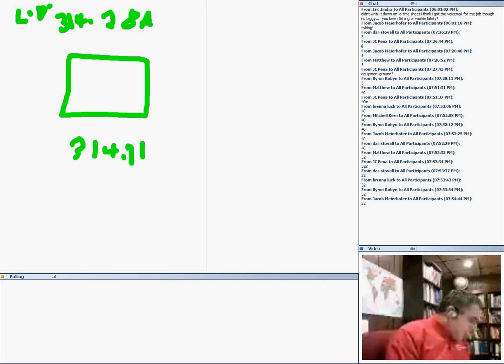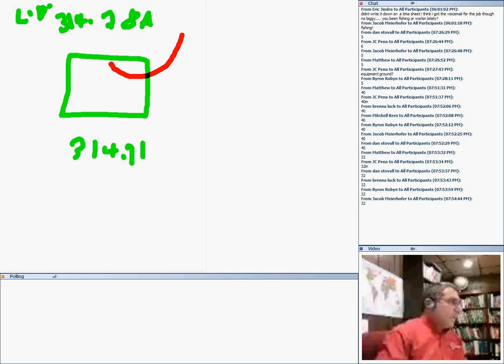All enclosed conductors and any splices or terminations present shall be listed as suitable for wet location. Very interesting. Handholes, guys, on the ground. You brought your cable in here. You terminate them. So there could be a wet location. This is for wet location.